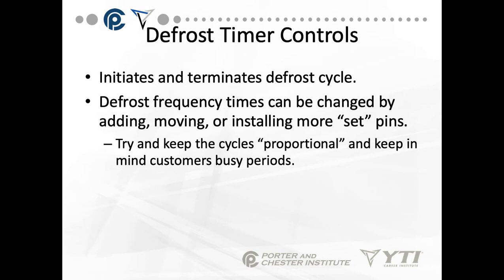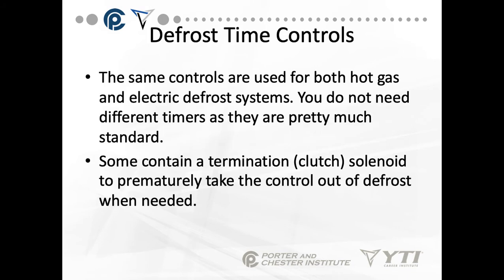The goal is to try to keep the cycles proportional — the same amount of time between the hours — and we want to keep in mind the customer's busy periods. For example, if we know that a restaurant kitchen is extremely busy between 3 p.m. and 11 p.m. and that refrigerator or freezer door is always opening and closing, we do not want to send our defrost during that time period.